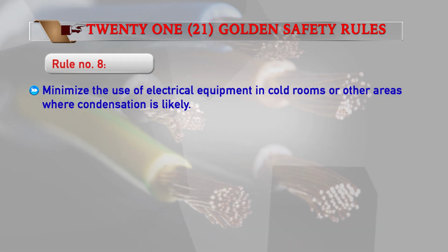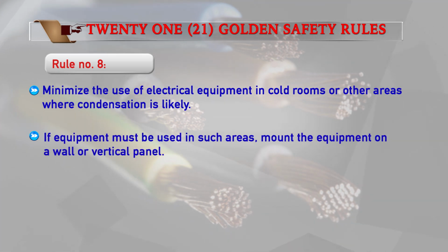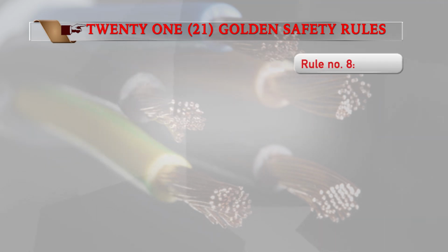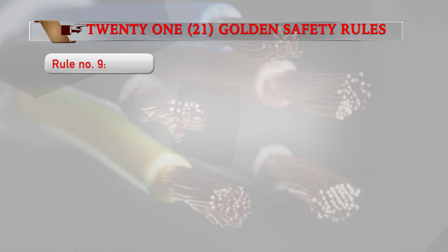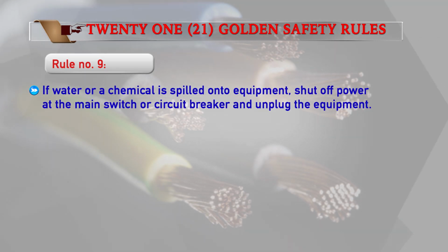Rule number 8: minimize the use of electrical equipment in cold rooms or other areas where condensation is likely. If equipment must be used in such areas, mount the equipment on a wall or vertical panel. Now, what is rule number 9? If water or a chemical is spilled onto equipment, shut off power at the main switches or circuit breaker and unplug the equipment. Never try to remove water or similar from equipment while appliances or lines are energized.